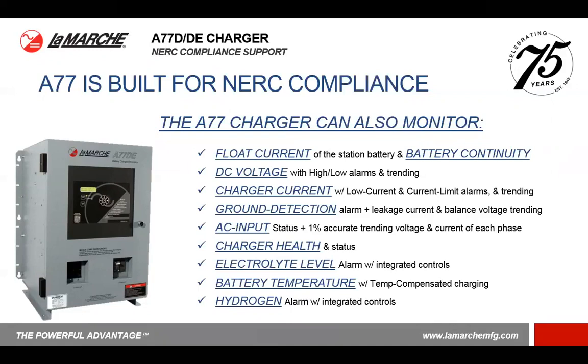For the AC side, it monitors the voltages and the currents, and it has the capability to monitor the voltage and the current for each phase individually in a three-phase configuration and provides alarms accordingly. For the DC side, it monitors the voltages, the currents, and any ground alarms or faults that could happen, and would provide alarms accordingly. For the battery, it has the capability to monitor the voltage of the battery remotely, monitor the hydrogen level in the battery room, the electrolyte levels of the batteries, and the battery temperature.